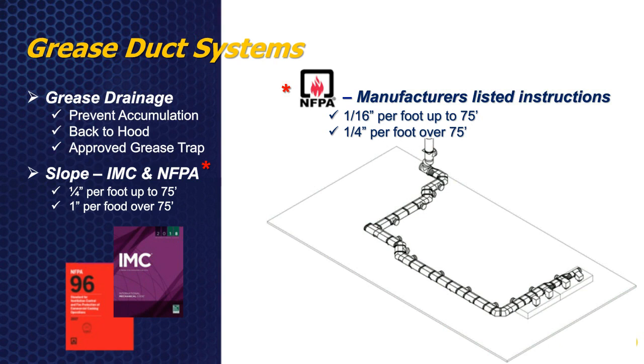So let's talk for a second about grease duct drainage. Per code, grease duct systems need to have provisions for grease drainage, and they are done to prevent accumulation of the grease inside the duct system. They need to drain back to the hood, which would be able to receive that grease, or back to an approved grease trap located somewhere inside that system. Now, the slope requirement to get this grease drainage is going to be noted in International Mechanical Code and NFPA as a 1/4 inch per foot on a horizontal run up to 75 feet in length. And if my horizontal run exceeds 75 feet in length, that pitch requirement or slope requirement will be 1 inch per foot. Now, there is a note in NFPA that if I utilize a UL listed manufacturer's product, I can refer to their listing instructions. UL allows factory built product to be done at a 1/16 of an inch per foot up to a 75-foot horizontal run, and then a 1/4 inch per foot if my run exceeds 75 feet.